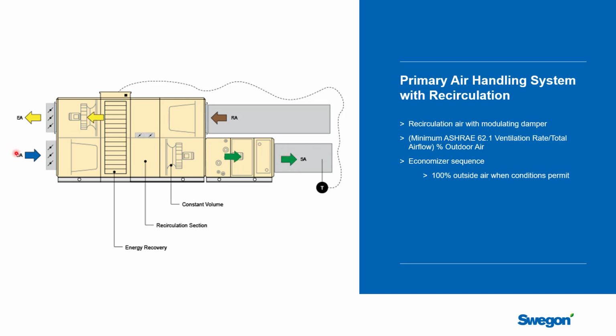So rather than bringing 100% outside air into the building, you may choose to recirculate some air through some form of mixing box. And if you do this, you're going to need a control sequence that makes sure that you deliver the prescribed amount of outside air. So either some kind of airflow station or some other control technology to make sure that you maintain your minimum outside air requirements to the space during occupied hours.